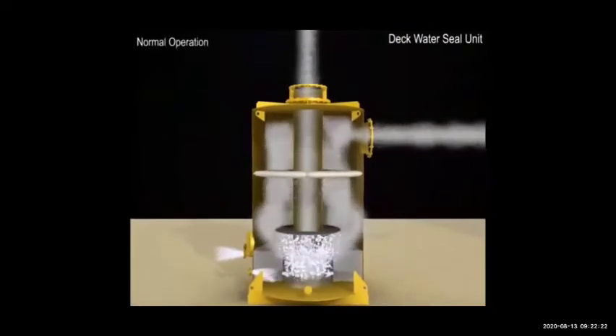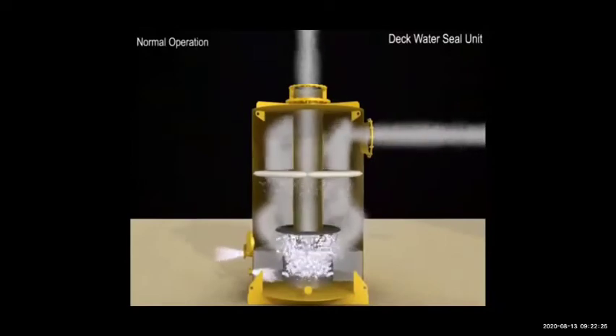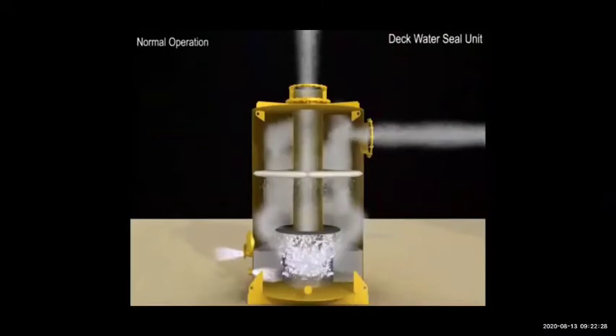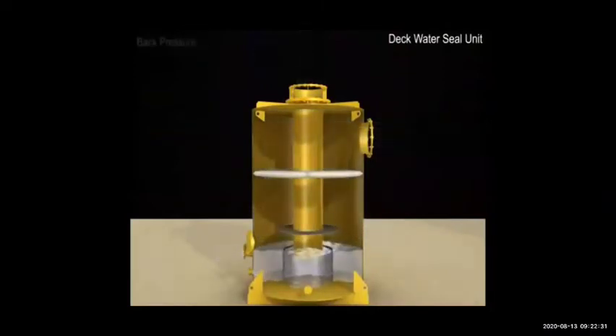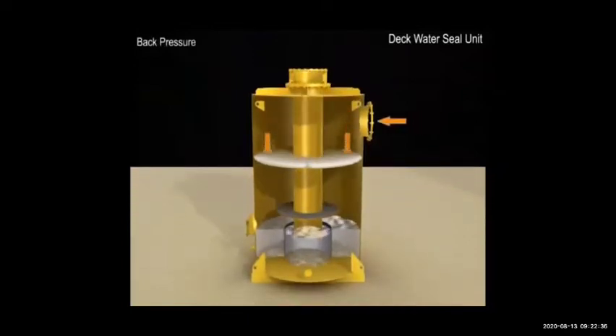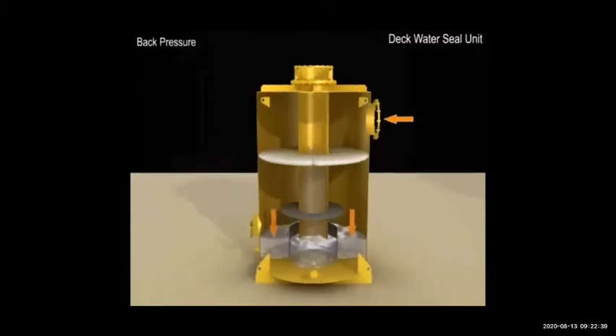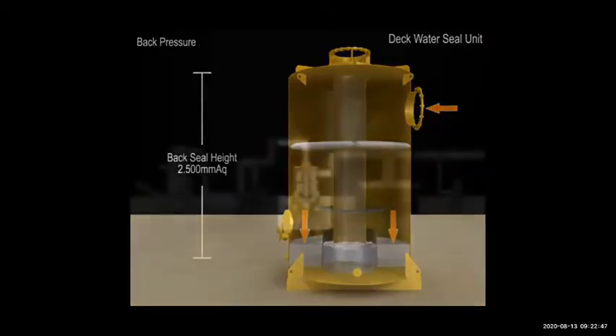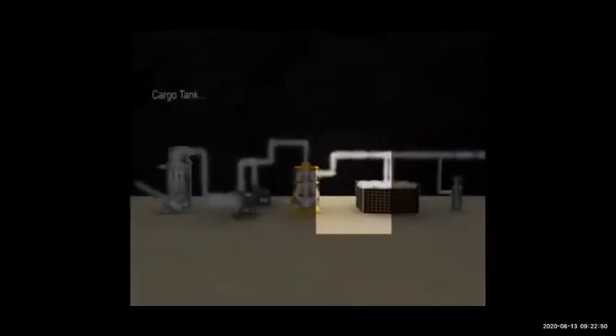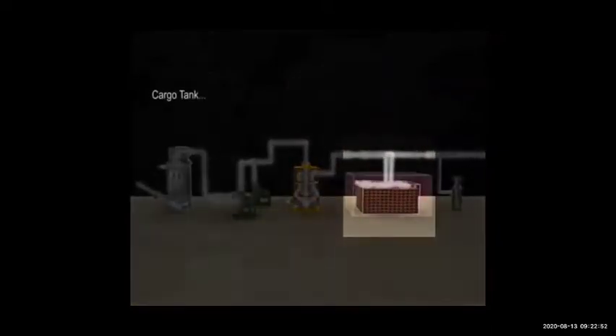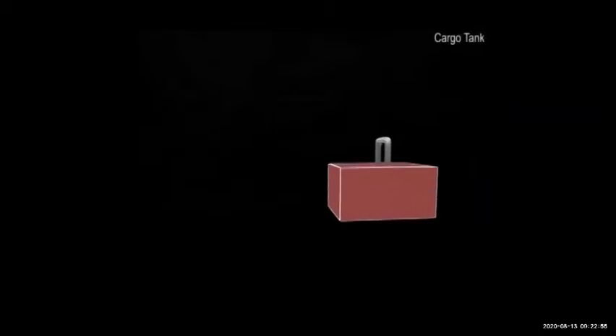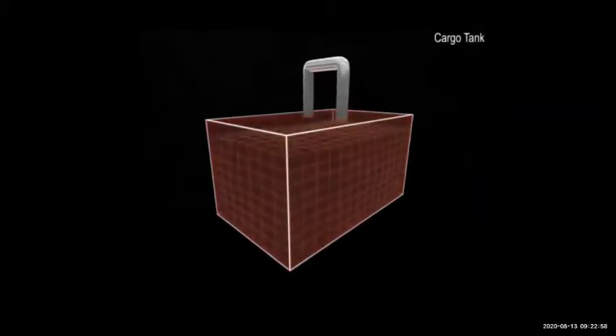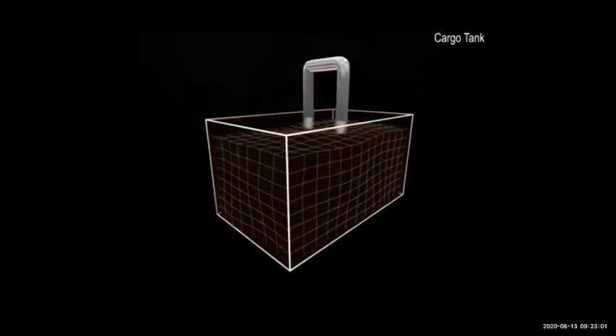Now if there is too much back pressure in the cargo tank and gas from the boiler side is at lower pressure, the gas will come and push the water in the deck seal. If it does not have enough pressure — 2500 mmWG is required — it cannot push the water. So the gas will not go back because there is a lot of water and gas cannot push it. That is how the deck seal works.